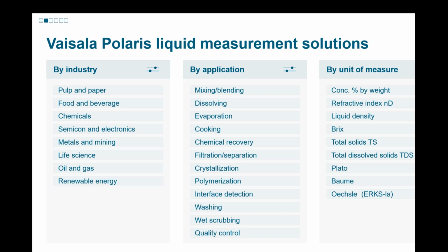Vaisala purchased a company called K-Patents about five years ago, and K-Patents has been around a long time. We've built chemical curves that convert the refractive index, the optical measurement, and correlate that to a chemical concentration for acids, caustics, and various other chemicals. If Brix isn't what you're doing, many scientists use refractive index alone and compare it to the CRC, maybe feeding it into their PLCs. But if you need a very specific chemical concentration curve, we can do that for you.